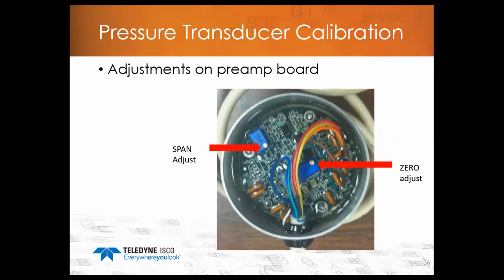And on the inside of the pressure transducer, once you have your cap removed, that will give you access to the circuit board. Now, on the pressure transducer circuit board, the board itself is covered with a clear potting compound, and that's to prevent any condensation or temperature changes that the pressure transducer might be seeing. It kind of insulates it from those.